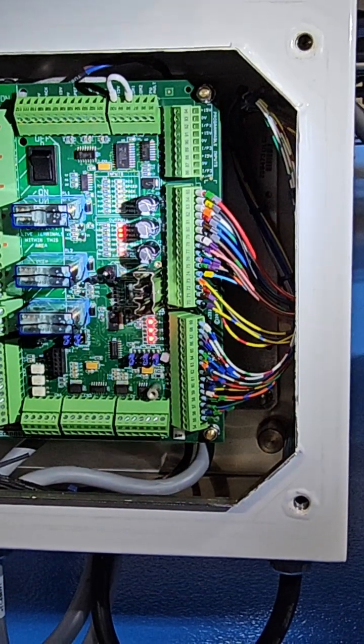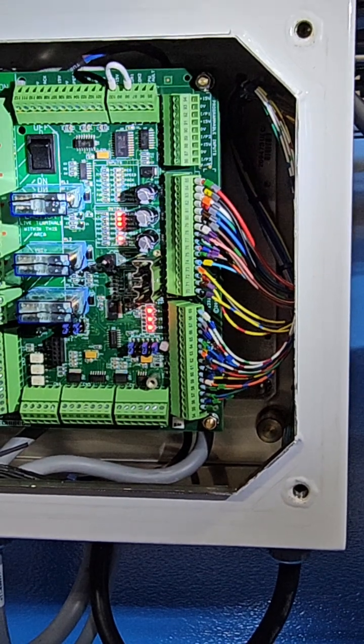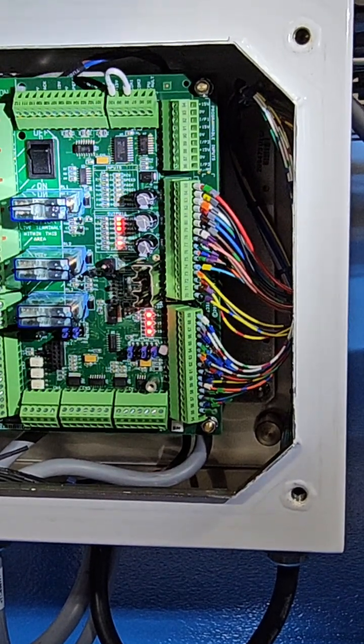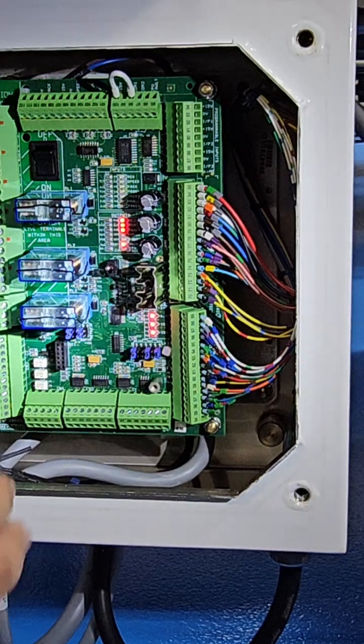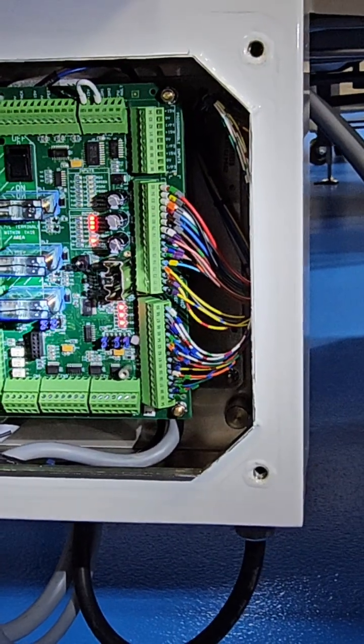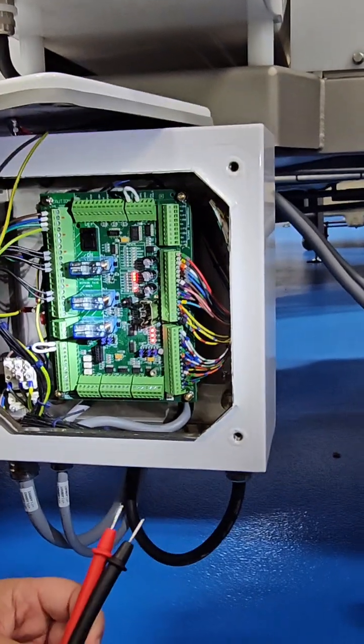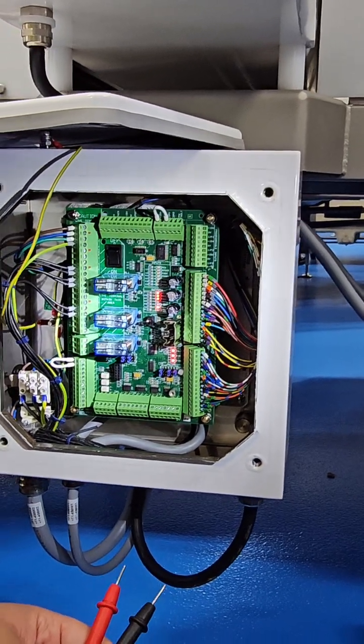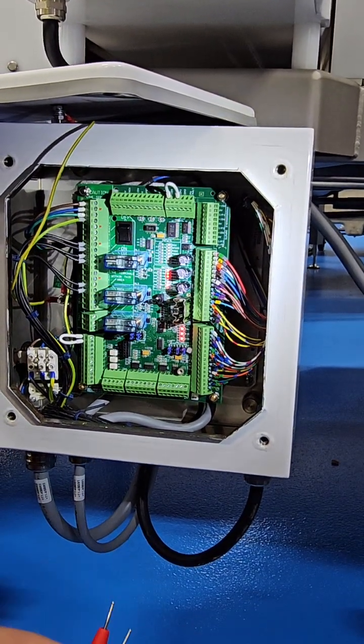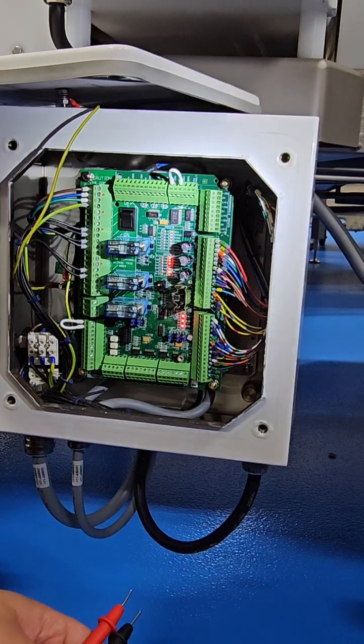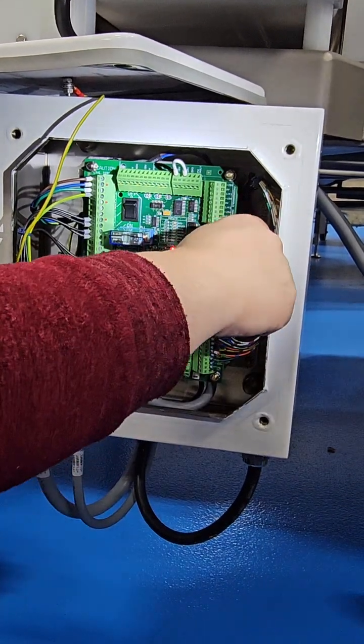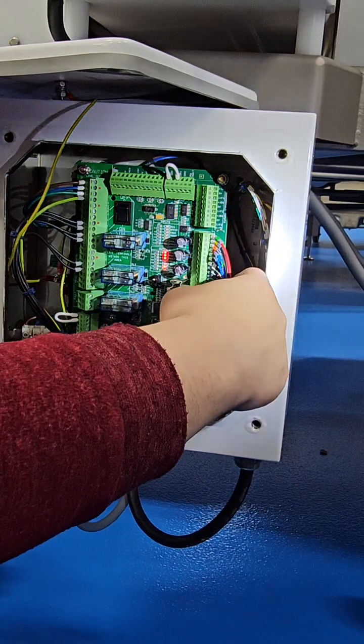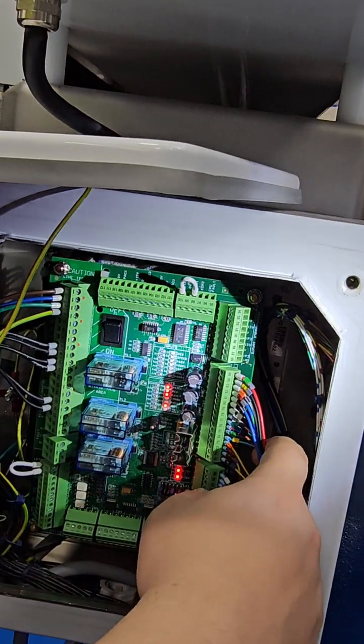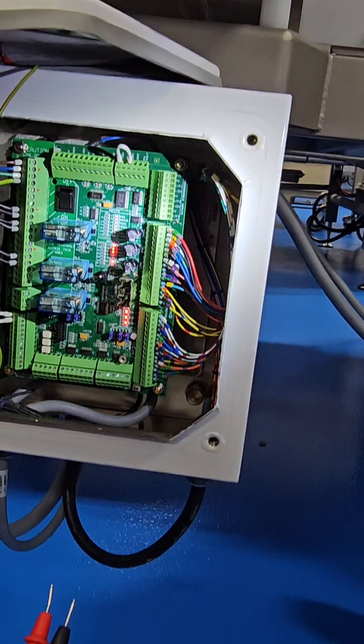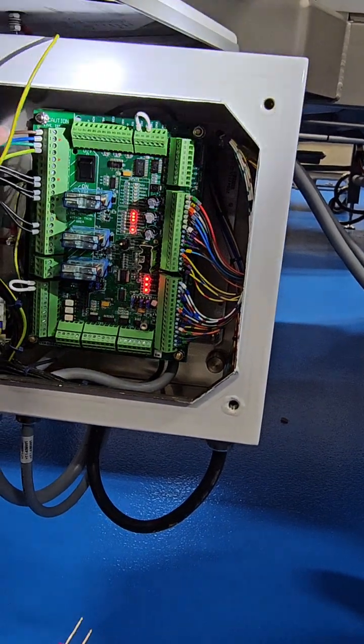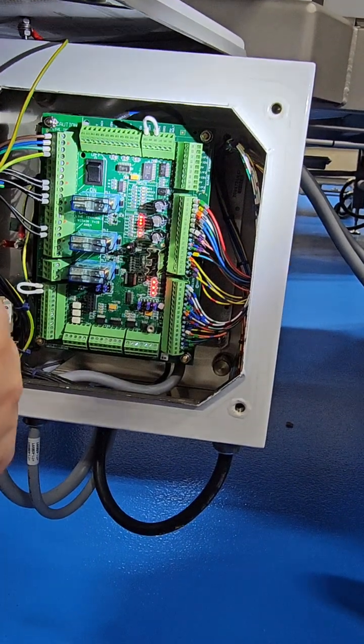If any of those four voltages are off, you need a new power supply. So honestly, that's pretty much everything we need to know about the power supply from a troubleshooting perspective. Generally speaking, even as a tech for this company, 99 times out of 100, if I have a power supply problem, I find it right here, on these voltages. I find it on my good in and my bad out. Good in, bad out, bad power supply.